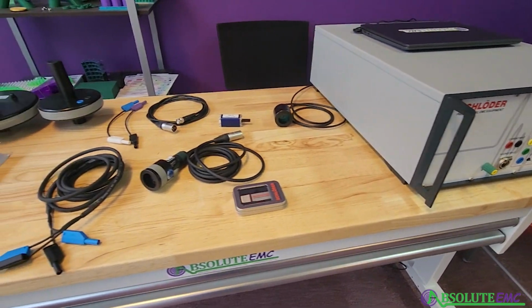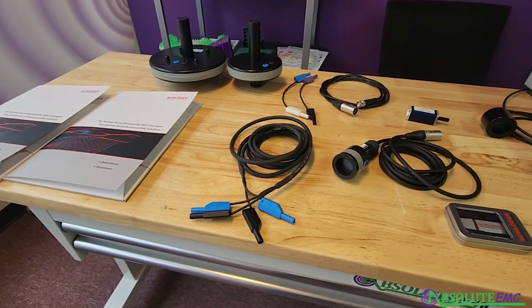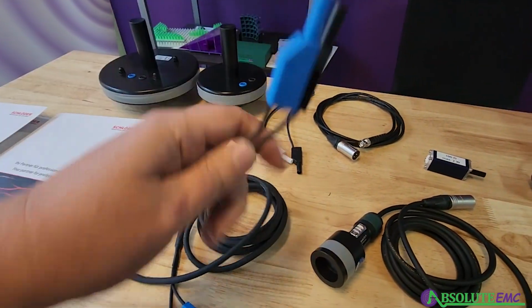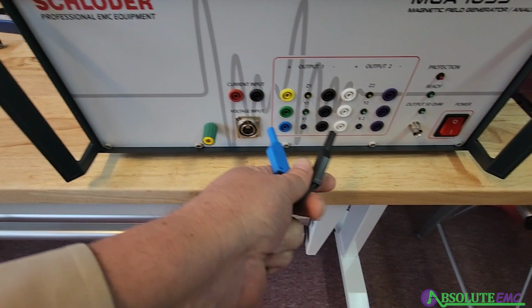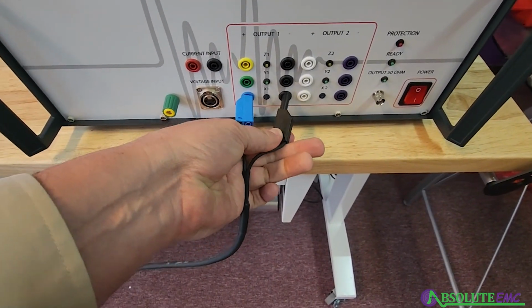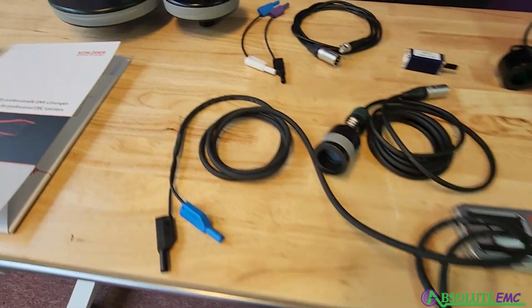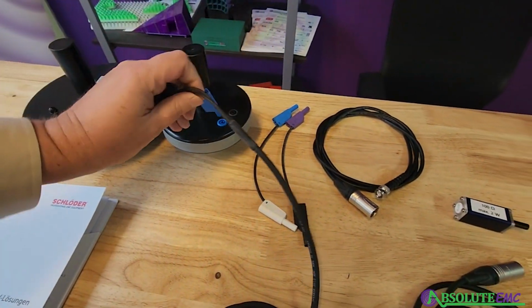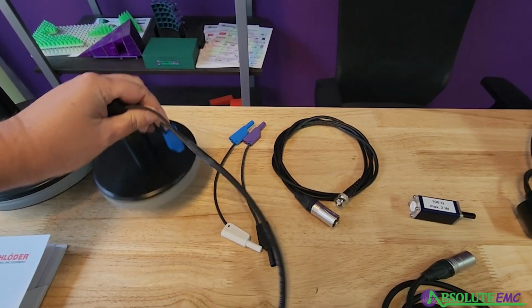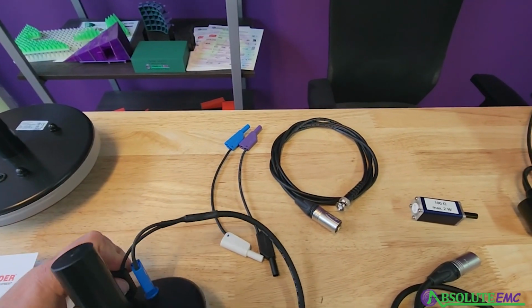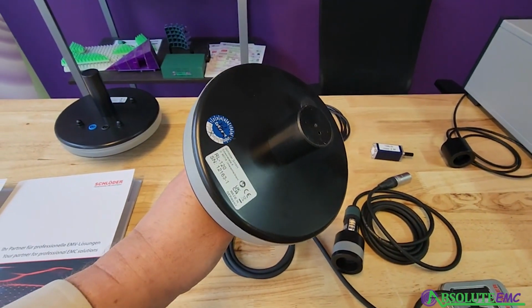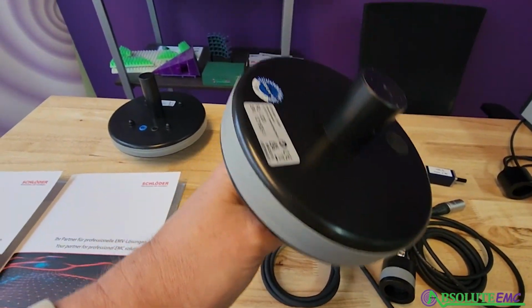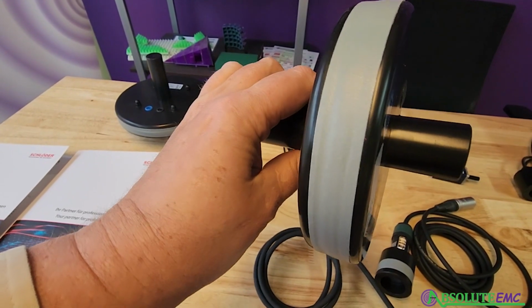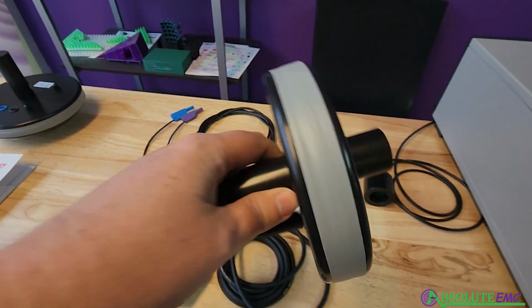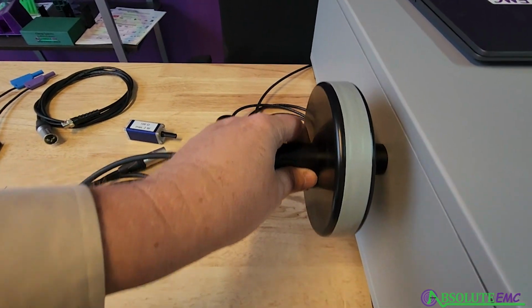So we're going to hook up the front with some measurement and radiating loops. So first we're going to hook up the radiating loop, take basically the color codes of the inputs here and go into X1. The other side of that cable, we're going to connect to our higher frequency radiating loop. It's hard to do this with one hand while I'm holding the phone. There we go. So in the radiating loop, on the one side there, we have a 5 centimeter standoff. That's commonly used in many standards. When you're testing a product, say this was the EUT we're testing or DUT, that gives you the 5 centimeters standoff.